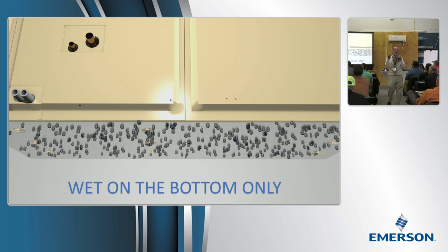We like water for exchanging heat, like chilled water or condenser water. But the thing to remember is that your insulation, when it gets wet, is no longer insulation. The same thing's true for the duct board - once it gets wet enough, it's going to run away from you, and you're not going to do anything about it until you come up with a strategy to either dumpster it or dry it out. So while they're standing there crying because everything's wet and going bad, you can just say, well, this is going to dry out in October - I promise, because it will. So the solution's on its way.